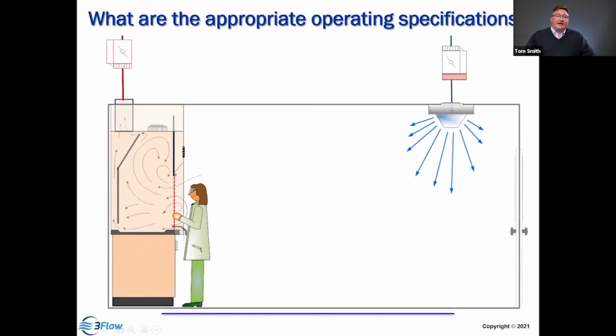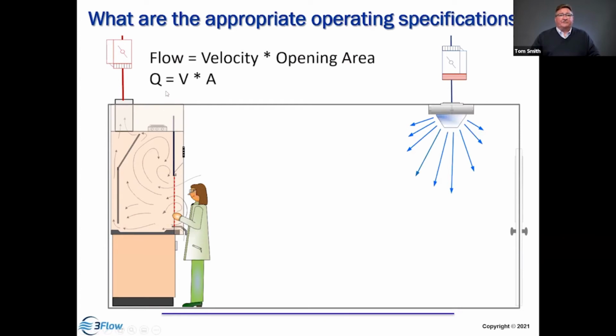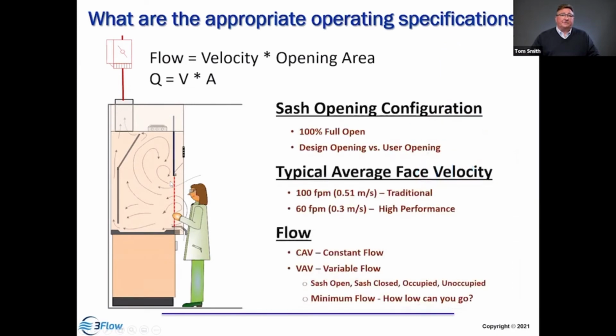We need to look at what are the operational specifications. If we have our hood operating and our air supply, we need to know what is the flow. And that's going to be a function of the face velocity when the sash is open. So we need to know the configuration of the sash. Is it going to be used 100% full open or at some restricted opening height like 18 inches? We need to then determine the average face velocity. 100 feet per minute is traditional, but a high performance hood could operate at 60 feet per minute.